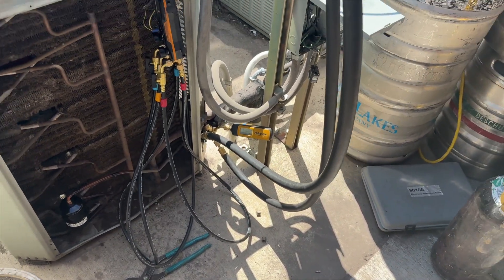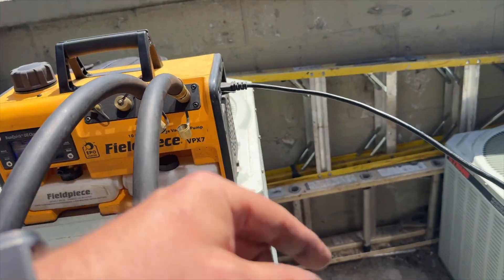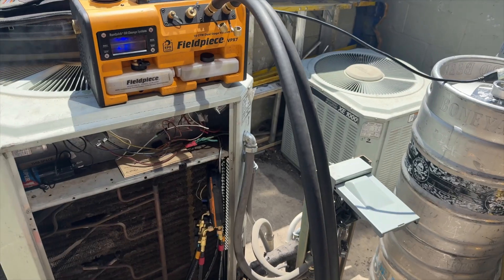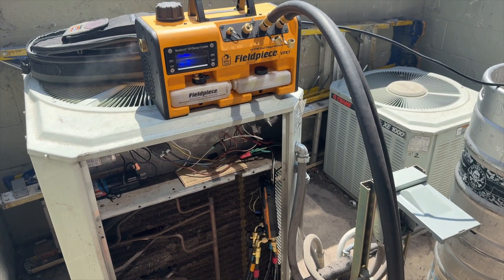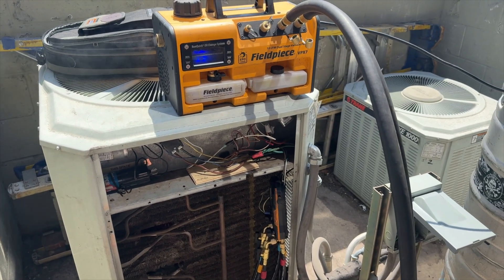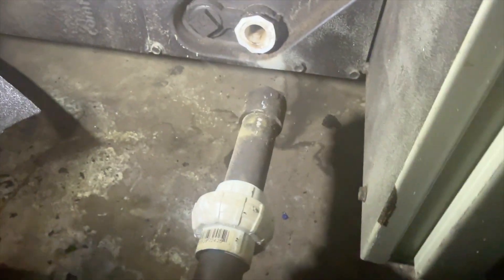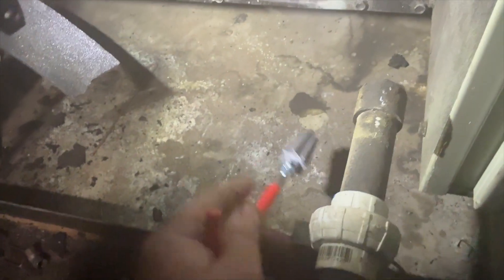We got her under vacuum — it's at 7,000 microns. Once it goes under a thousand I'm going to close the ballast; usually I'll leave it open until it hits under a thousand. These Fieldpiece vacuum pumps really pull. We can see here that the drain fitting is busted, so I can use this extractor tool to get it out.